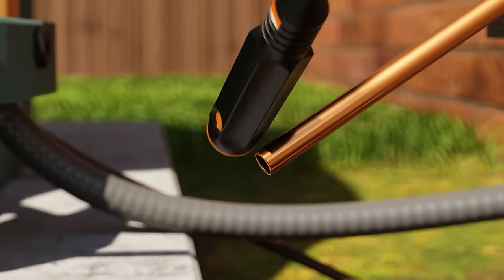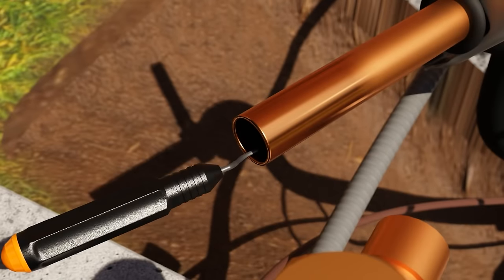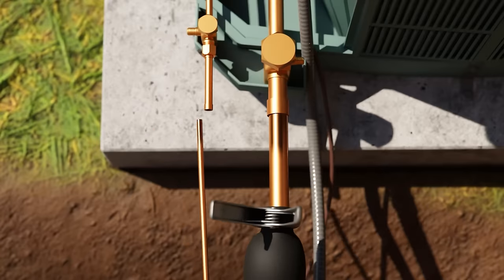Here we show tipping the copper downward and tapping it with the back of the deburring tool to ensure that no shavings fall into the tube. Also make sure not to over-deburr in cases where you're going to make a flare connection. This can thin out the edge and cause cracking.